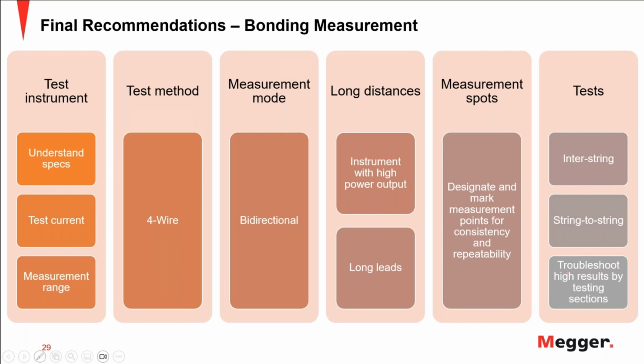And what tests to perform: interstring, string to string, and then you want to troubleshoot high results by testing different sections. So you start dividing and conquering, basically. So this is about the bonding testing, the low resistance measurement. As I mentioned before, the presentation is heavier on the bonding side. But now let's move on to the insulation resistance.